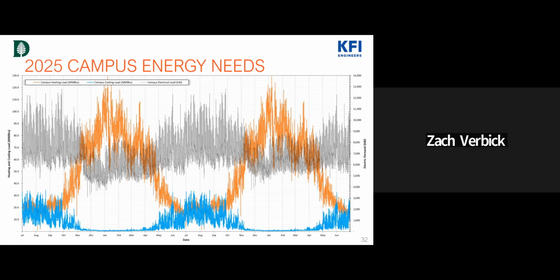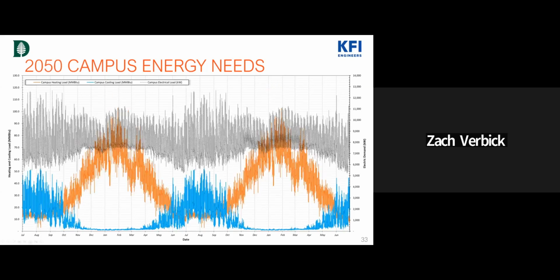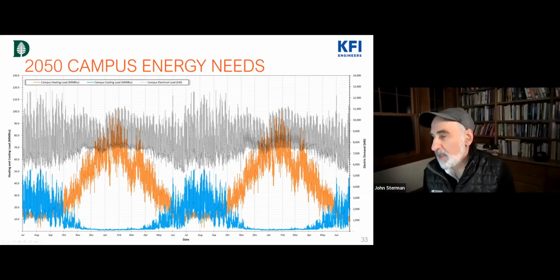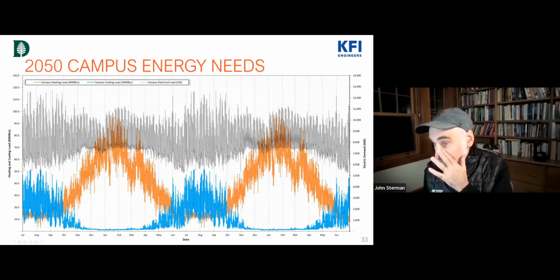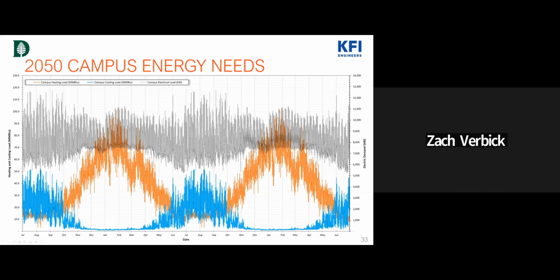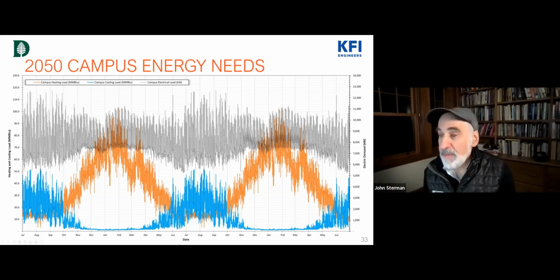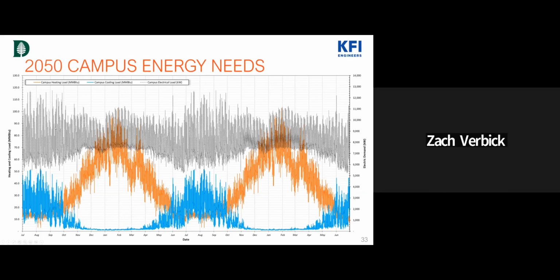Looking towards the full build out and overall impacts, everything we're doing reduces the heating peaks on campus, and that has an impact upwards throughout the system. You can see the orange line has dropped. Our blue lines have increased because we've added a significant amount of cooling, but that's not a big deal in terms of electrical demand. We'll get into a couple of charts after this that show why we're seeing what we're seeing. In the winter, inevitably our electrical load has gone up, but the peaks are lower in summer, and the minimums are higher.